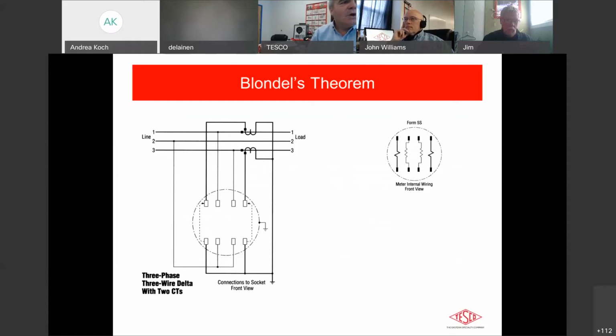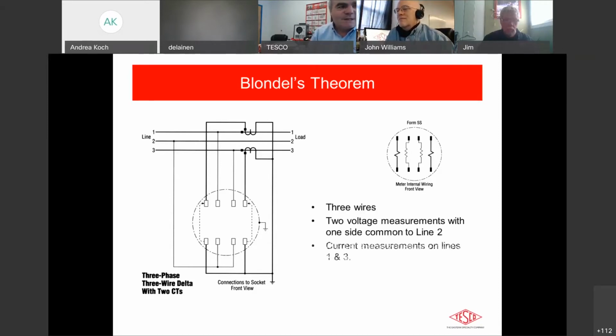Mm-hmm. All right, so here's Blondel's theorem in practice. This is a 5S meter. We've got a 3-phase, 3-wire delta with 2 CTs. You click on that, John, you'll get a little bit. There you go. Now the 2 voltage measurements, one side common to line 2, current measurements on lines 1 and 3. This satisfies Blondel's theorem. So in this case, we've used a 5S meter in a 5S service, and we did it correctly.